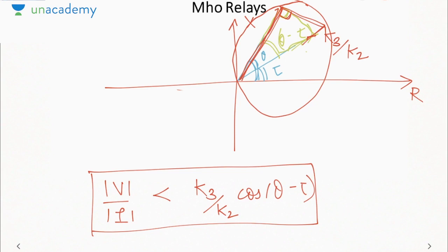So the angle in a semicircle is 90 degrees. That means all the points within this circle will lie in the trip region. Outside we will have the block region. Why? Because mod Z must be less than this length, so all the points will come under this region. That is how we draw the characteristic of the Mho relay. The characteristic of this relay is not that trivial, so it is better that you memorize it, but just remember how we have drawn it.